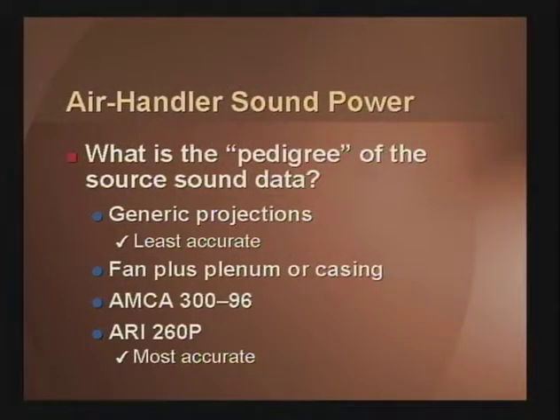As you can also see, it's very important to start with good quality source data. Unfortunately, there are varying degrees of quality of sound power information for air handler units in the industry today. This slide tries to explain the pedigree of the sound source data, which ranges all the way from generic projections, which are not based on any test data, but are typically using the ASHRAE algorithm method for fan sound prediction that some manufacturers still use. One level of improvement beyond that would be to use an algorithm method for trying to take into account the effect of an air handler unit configuration in addition to just what the fan sound is.